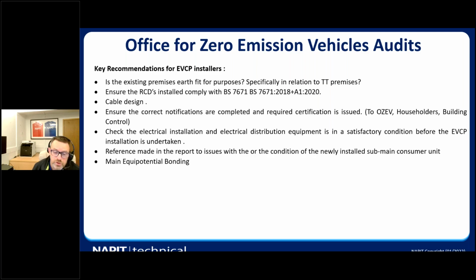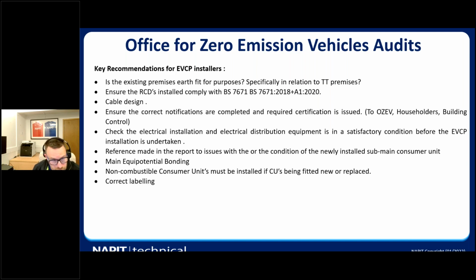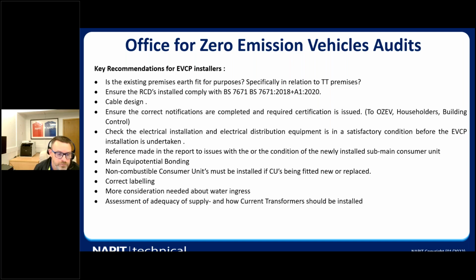References are made in the report to issues where the condition of the newly installed consumer unit, the main equipotential bonding, non-combustible consumer units must be installed if new CUs are fitted as new or they're going to be replaced. All the correct labelling is in place to cover the EV charge point and any associated equipment. And consideration is needed for water ingress with the EV charge points, cabling as it exits the building, things like that. And assessment of adequacy of supply and how current transformers should be installed.